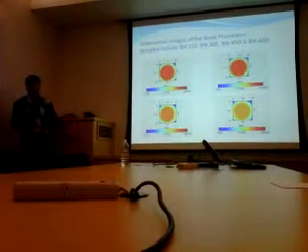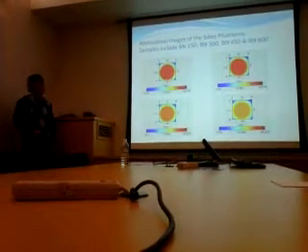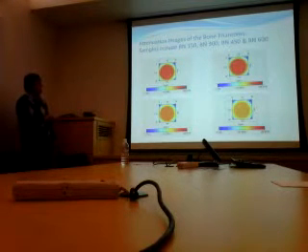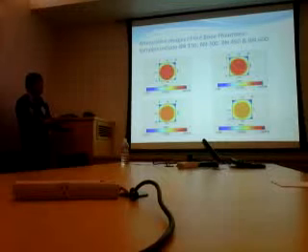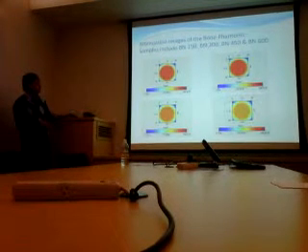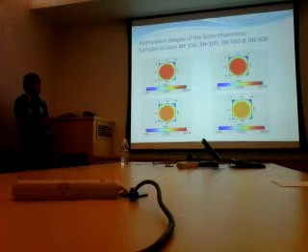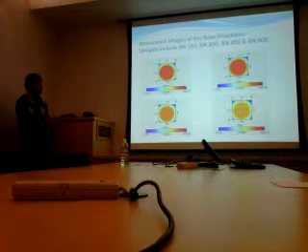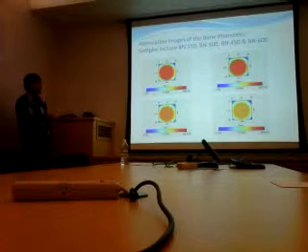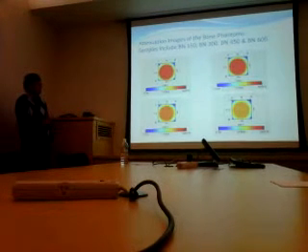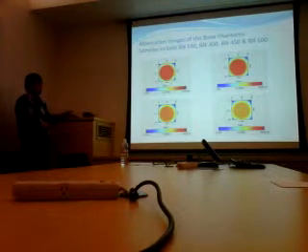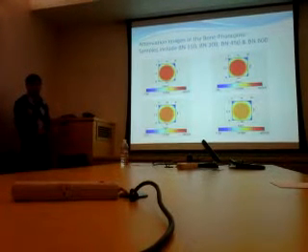Here are some color-coded attenuation images that we take with our scanning system. The image in the upper left is our lower end density phantom, about 150 milligrams per cc, and in the bottom right is a phantom of 600 milligrams per cc. As you clearly see from the color-coded images, as you increase density, you also increase attenuation.